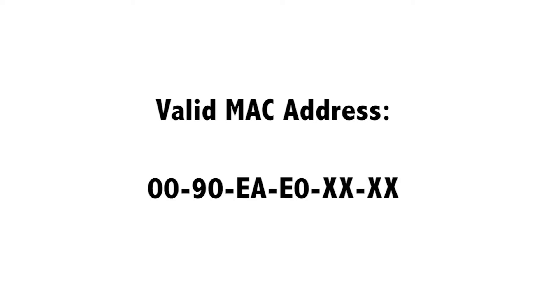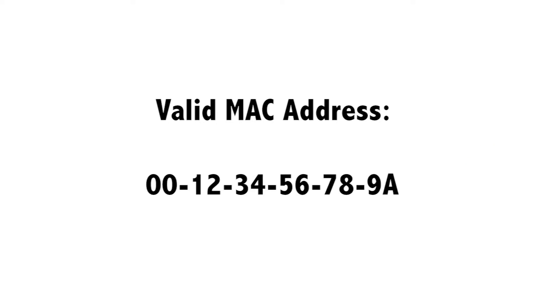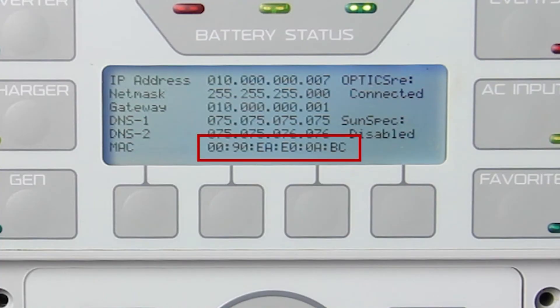Next, verify your Mate 3 has a valid MAC address. A valid MAC address starts with 0090 EA E0. If your MAC address appears to be 00 12 34 56 78 9A, this Mate 3 needs to be replaced. To check, press the port button from your Mate 3.